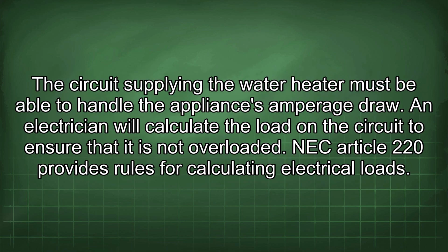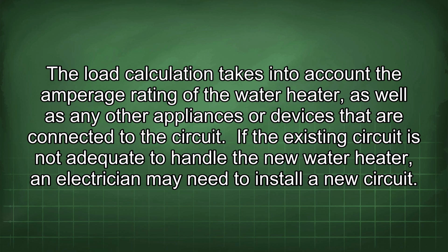The circuit supplying the water heater must be able to handle the appliance's amperage draw. An electrician will calculate the load on the circuit to ensure that it is not overloaded. NEC Article 220 provides rules for calculating electrical loads. The load calculation takes into account the amperage rating of the water heater, as well as any other appliances or devices that are connected to the circuit.